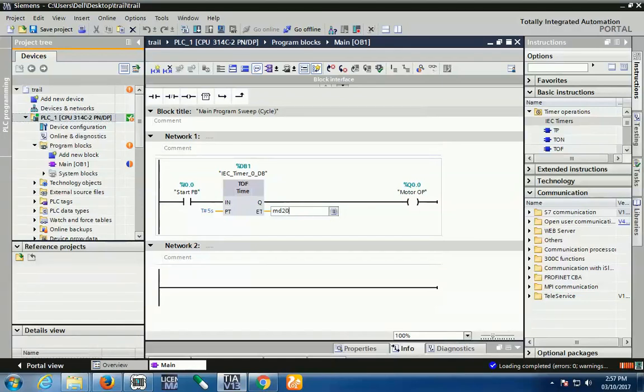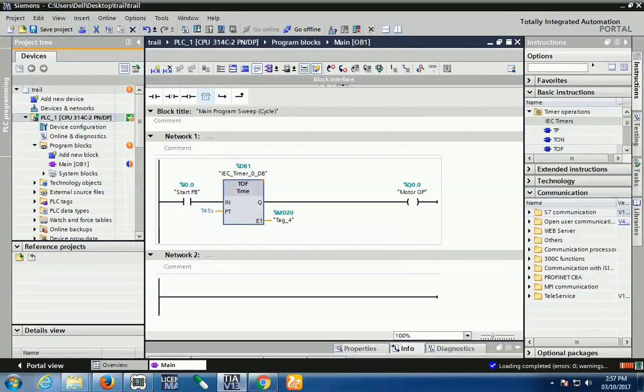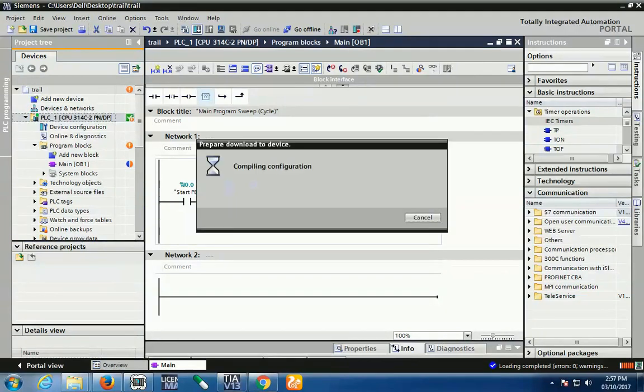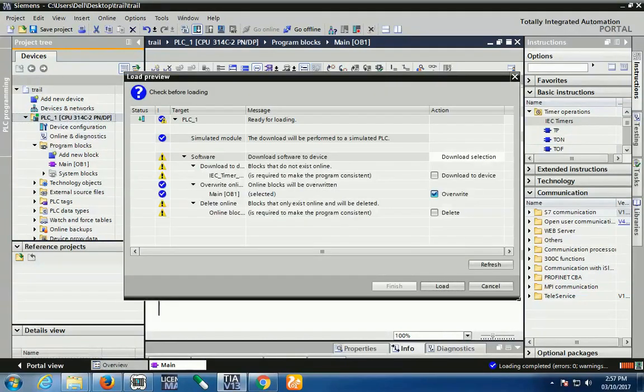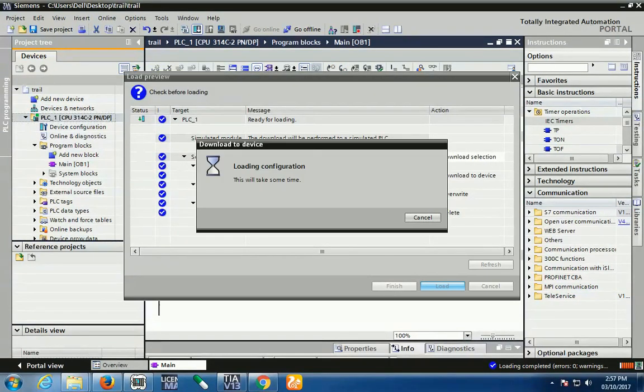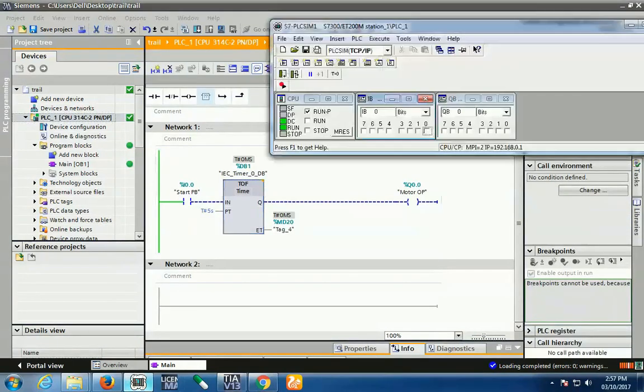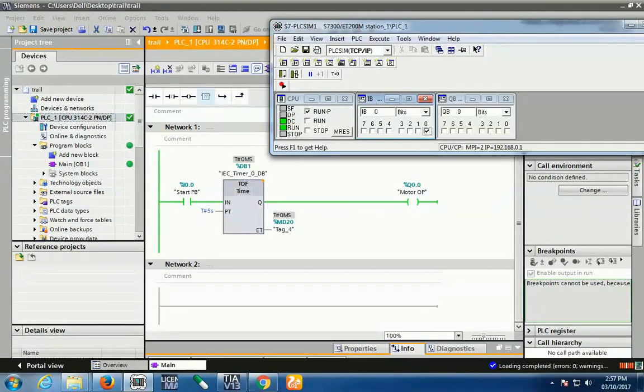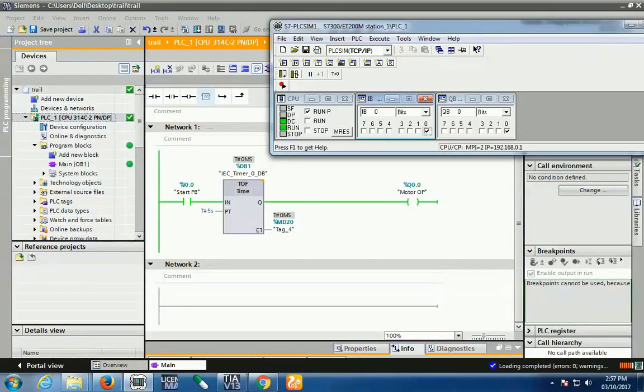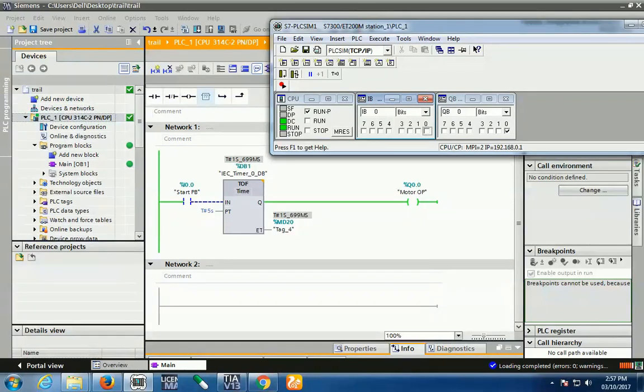Your configuration is completed. Let's see. If I press the start button, my output should turn on, and when I release this start button, my motor should turn off after 5 seconds. Now you see I release the input, time starts now, and after the time completion my motor output should turn off.